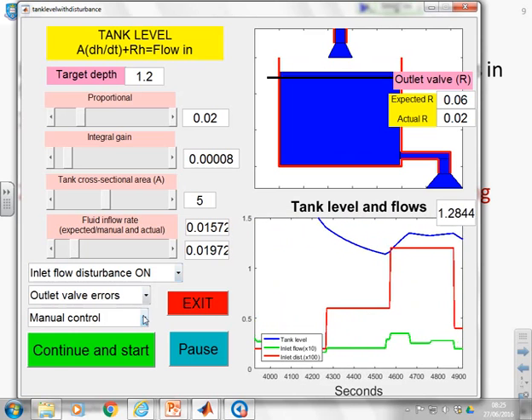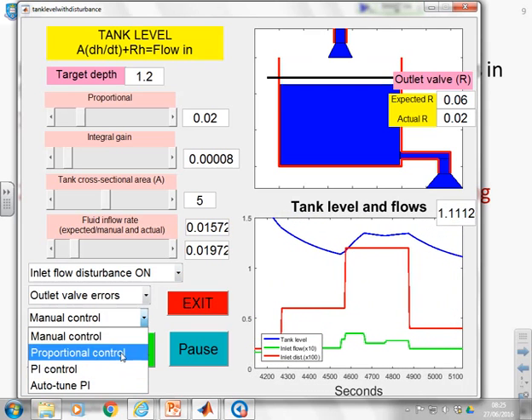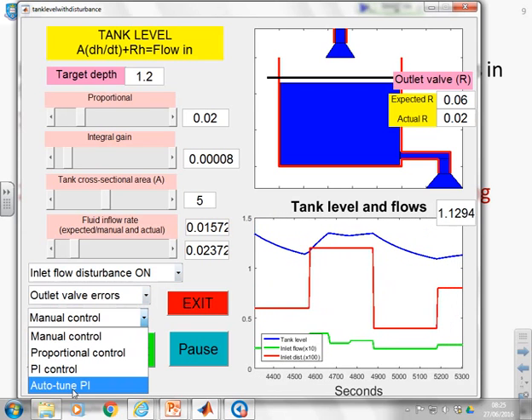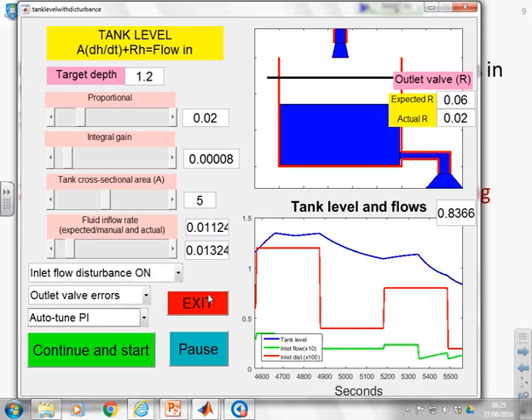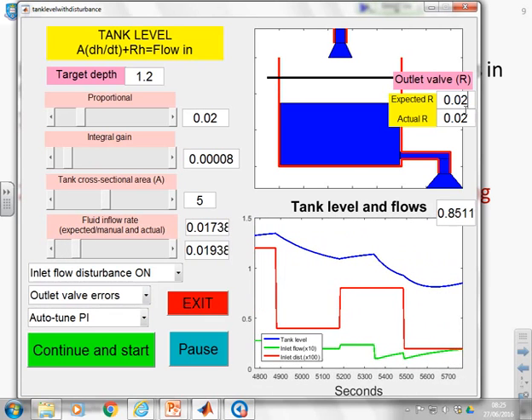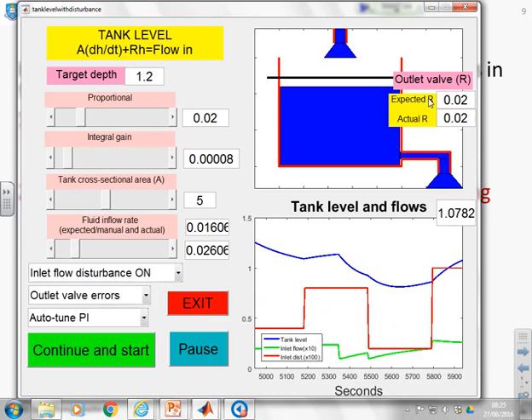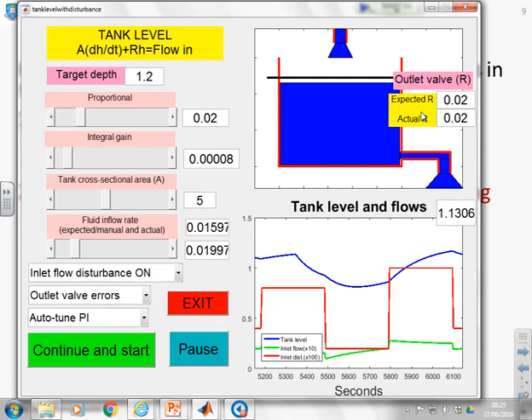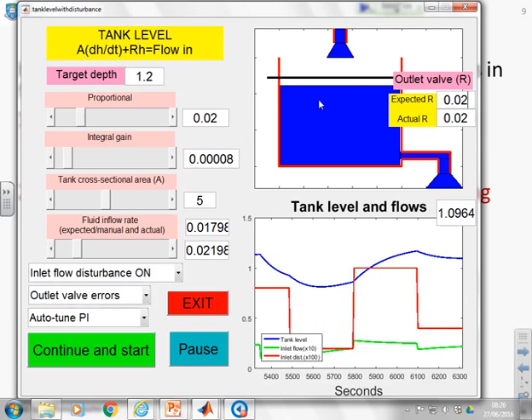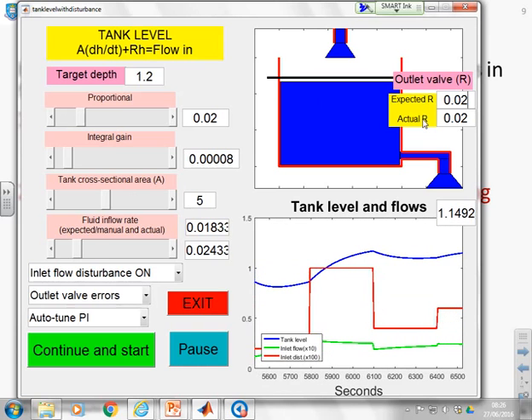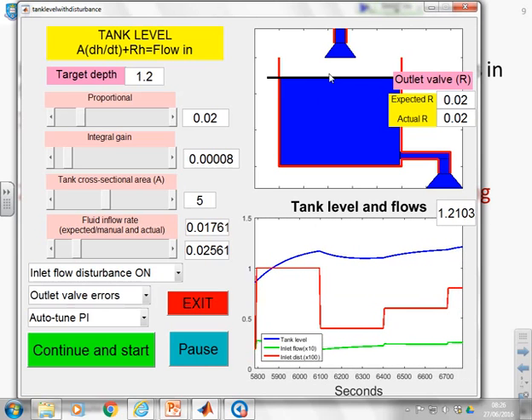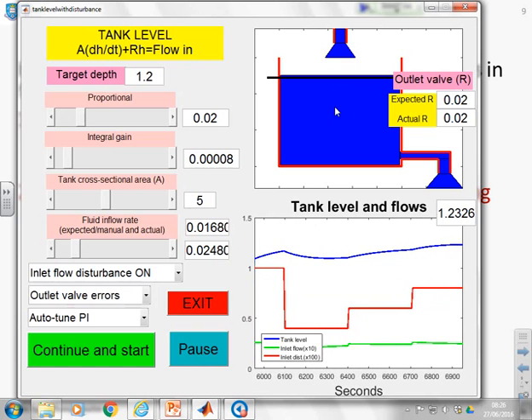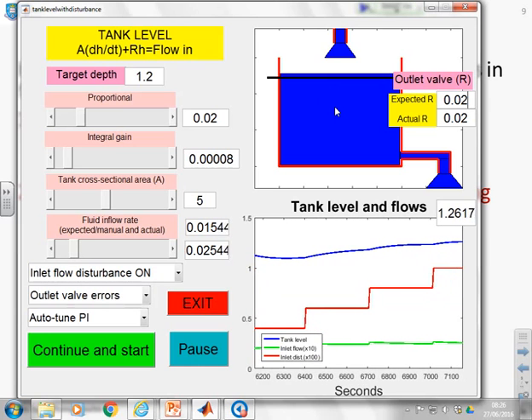So what I'm going to do now is switch to auto-tune PI. You'll see there's an option PI control. If you choose the option PI, it will choose the P and the I from these sliders, so you can do it yourself. I'm going to do the auto-tune just to demonstrate that it works. So you haven't got a bumpless transfer, so in the first instance it will... Oh, and because the expected and the R are different, the auto-tune obviously works on the expected R. So if those are very different, the auto-tune may not do a good job. And that's something else you can look at. The auto-tune is picking up this area and it's picking up the expected R. So if there's big errors, the auto-tune won't work very well. But now you can see it's not doing too bad a job. You'll see we're getting the level roughly to where we want, and whenever we get perturbations, you'll see pretty much it's keeping you at the level that you want. So it's doing a fairly good job.